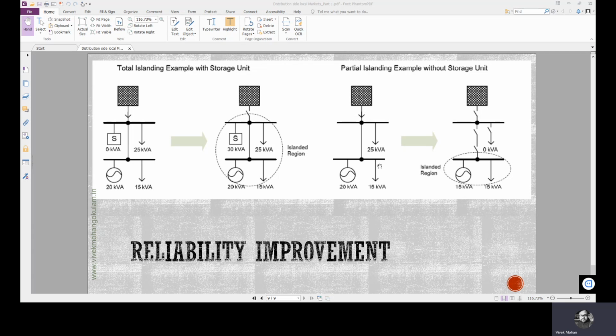Now in the third case, that is the partial islanding case. In this case two loads are there, 25 plus 15, 40, and 20 kVA local generation is there. So total load cannot be met from the local generation. So extra power should be tapped from the upstream grid. In this case, we cannot fully island the system as we don't have a storage device here, because if we totally island the system, then 40 will be the demand and 20 will be the generation. There is no normal operation then.